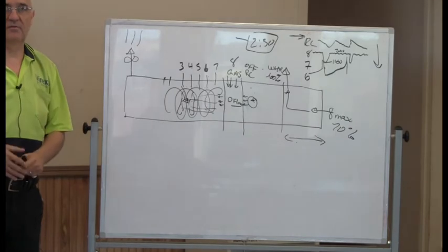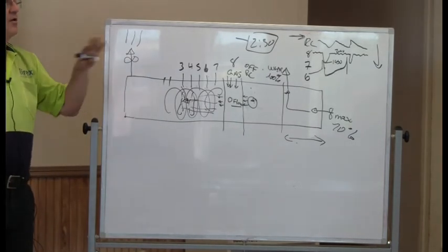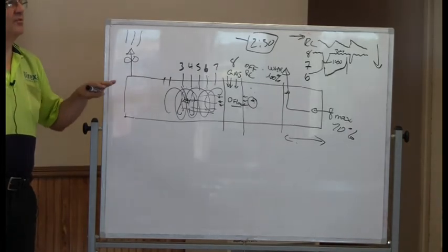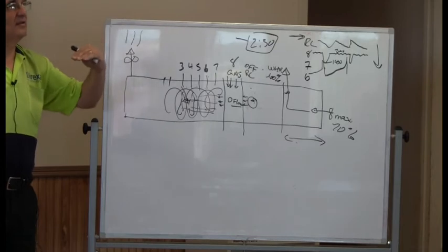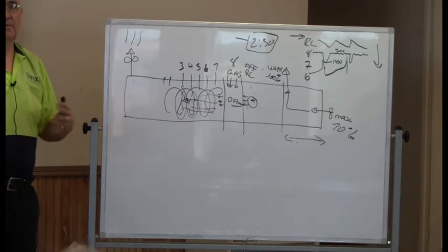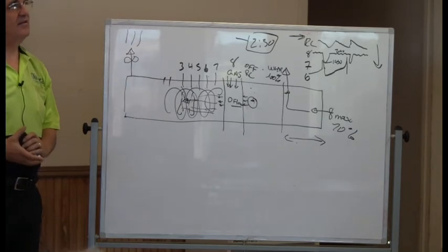Start your gas. And you always start your gas only when all your fans are in the position they are supposed to be. Right. Don't start the gas while everything is traveling, because then you start burning, getting excess heat, etc.